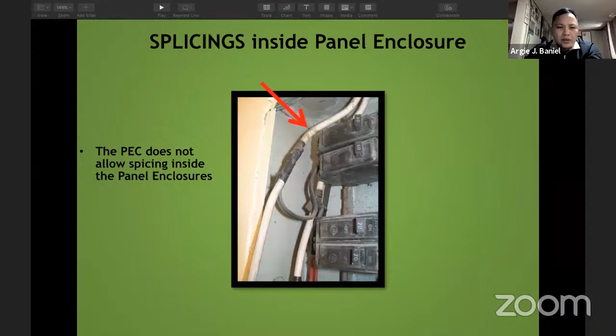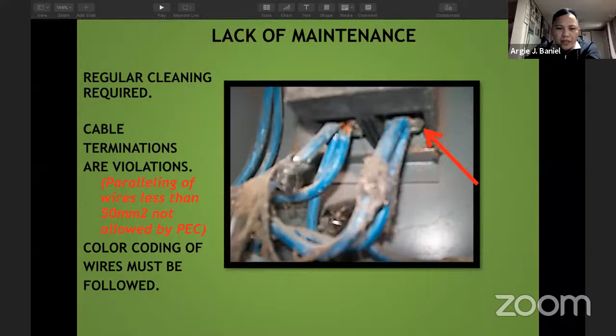Splicing inside the panel board enclosure. The PEC does not allow splicing inside the panel board enclosure. Regular cleaning required. The cable terminations are violations. Paralleling of wires smaller than 50 square millimeters is not allowed by the Philippine Electrical Code. And color coding of wire must be followed. Transformer pad, no danger sign. High voltage, so there is none of that. Danger, high voltage, or electrical shock hazard.